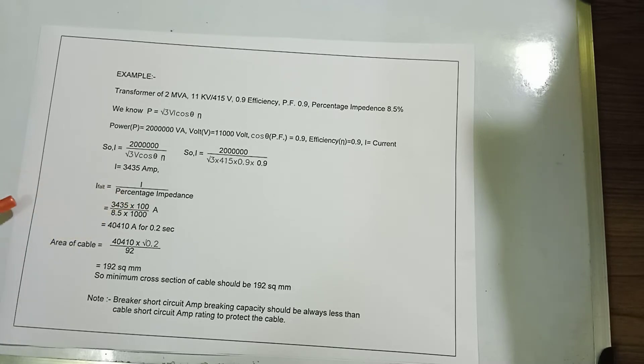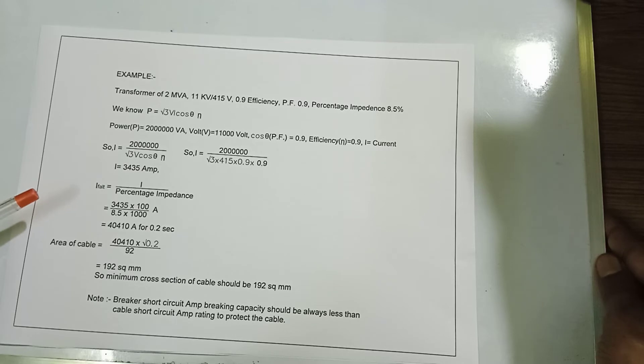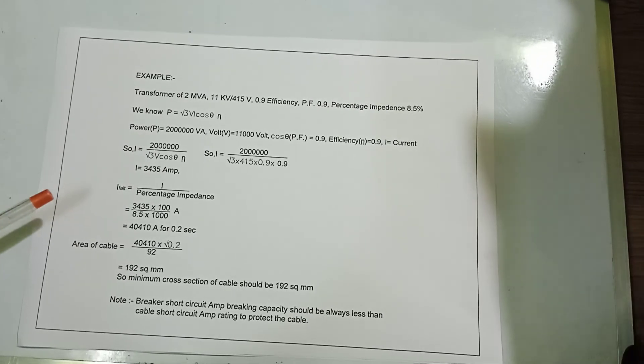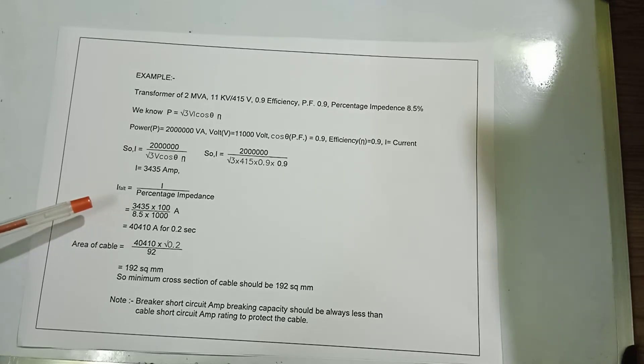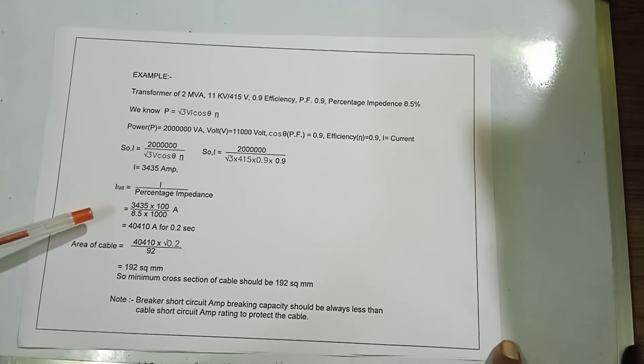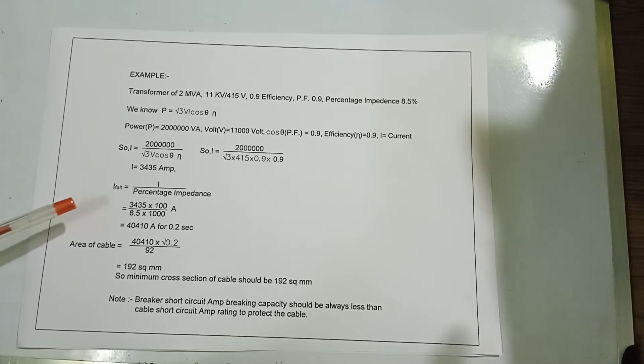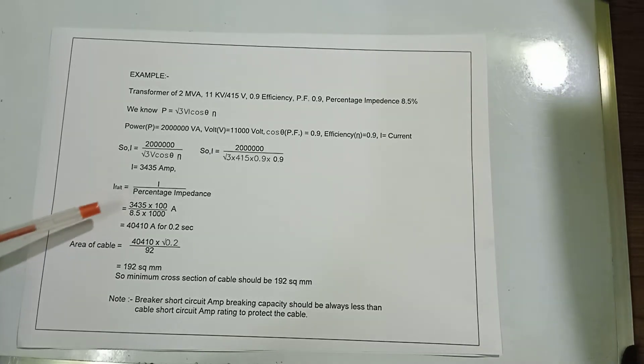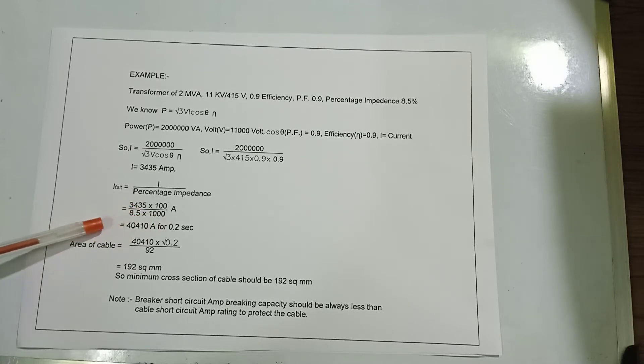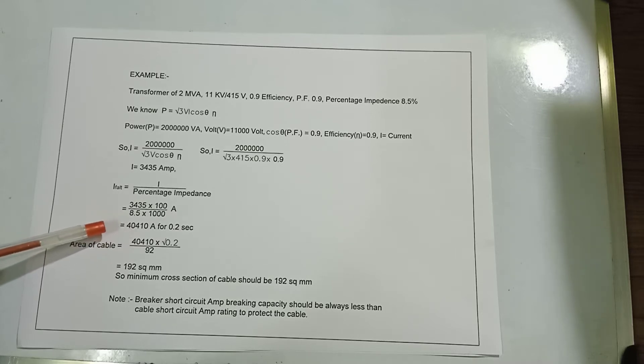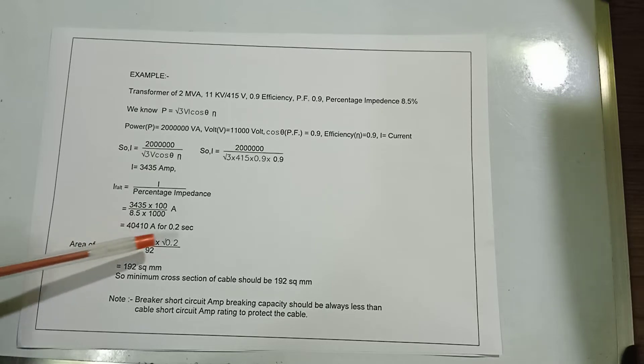The fault current I_fault = I divided by the percentage impedance = 3435 × 100 / 8.5 = approximately 40,410 amperes. This applies for a fault duration of 0.2 seconds.